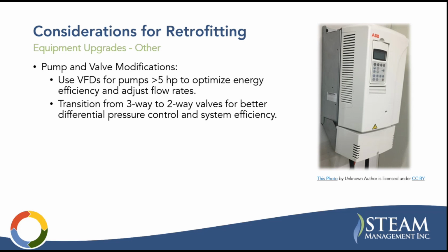Other considerations: pump and valve modifications. You want to use VFDs on pumps greater than 5 horsepower so you can optimize your energy efficiency and adjust flow rates. You want to transition away from three-way valves to two-way valves. Again, this doesn't always happen. You can use that outdoor reset instead and operate in a similar fashion to how you've been operating and still get some benefit out of that. But adjusting away from three-way valves, where they're bypassing at the different users, just reduces the amount of blending in your return water.